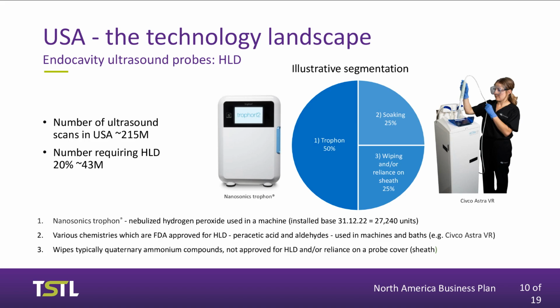And then there's a third category of scans and the method by which they're disinfected or not disinfected, which is the unauthorized, non-compliant practice that exists in the United States, as it does in all other countries. There will be wipes that are used that are not of an appropriate classification. In other words, they're not high-level disinfectants. And in quite a number of instances, the sonographer or the healthcare establishment will be relying upon a sheath or a condom to cover the probe as it goes into the patient and presume that it acts as a barrier to stop the transmission of pathogens from one patient to another. It's not an appropriate methodology. It's not acceptable to the regulators, but in some instances, it's just done.